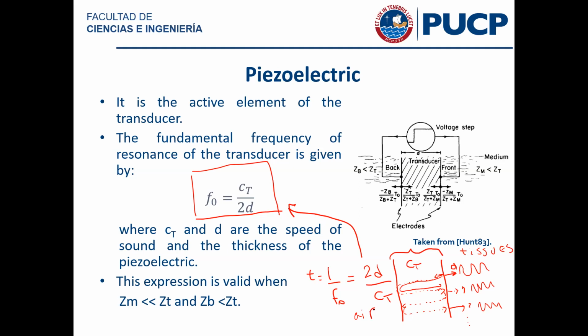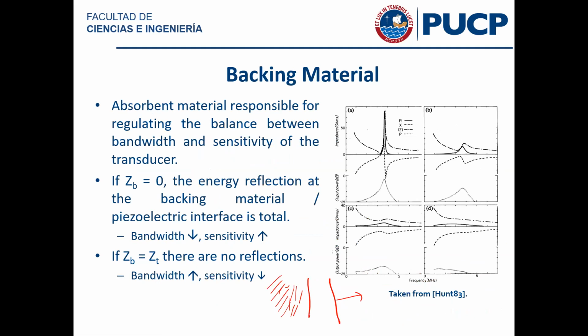That's what would happen if you just were to grab the piezoelectric element in isolation. Sure, no problem. So what we do in practice is we don't put air. What we do is we place another material in here, which we call the backing material.